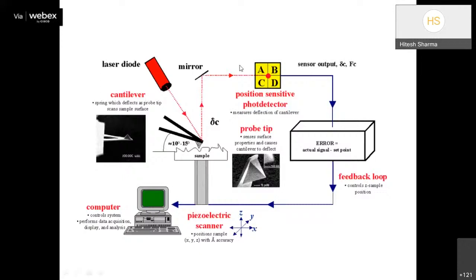This complete diagram explains the principle and working phenomenon of AFM. It shows the PZT scanner, the sample placed over it, the cantilever and cantilever probe, the laser diode, the position sensitive photodetector (PSPD), and the feedback controller that manages error signal or error voltage and provides feedback signals back to the scanner to adjust direction.